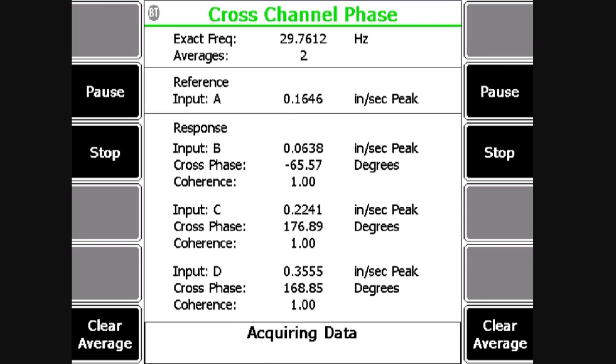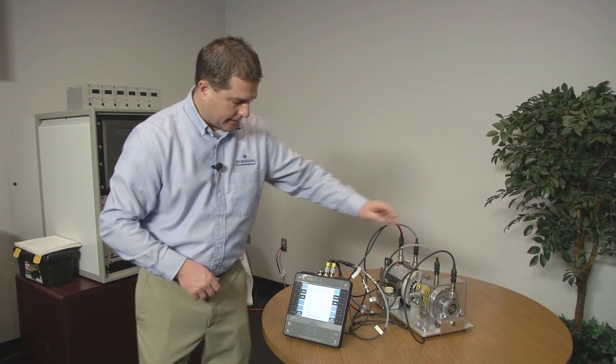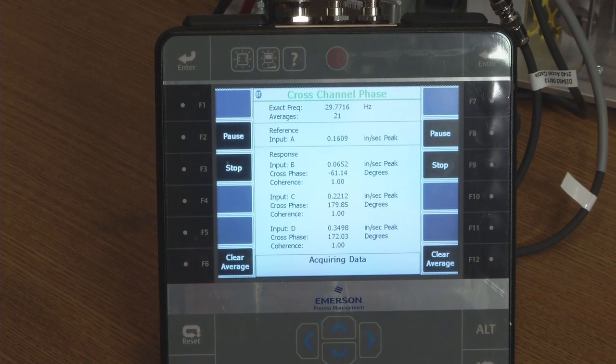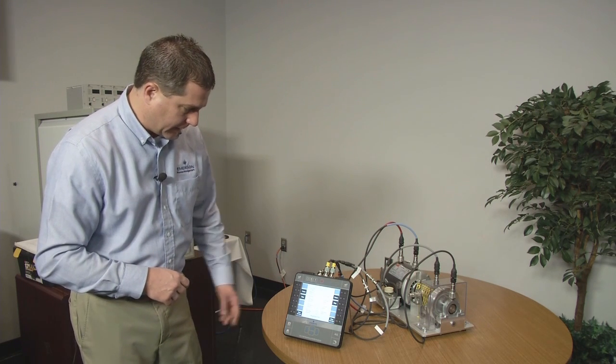So now I've got channel A as my reference. And then I'm seeing the cross-channel phase and coherence for channels B, C, and D. So my red is A, blue is B, gray is C, black is D. And so you can see my coherence is one for all of them. That means they're all receiving the same vibration from the same source because they're all on the same demo kit here.